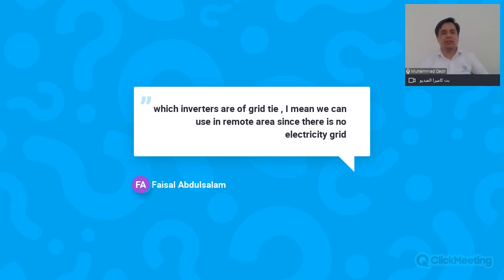The first question is from Faisal Abdul Salam. He asked, what inverters are off-grid? I mean, can we use them in remote areas, since there is no electricity grid? Faisal, on-grid means these inverters require the grid at all times to provide an output. So inverters for an off-grid area are different compared to the inverters we spoke of today in the installation mode. Huawei will soon launch such inverters which can be used for remote locations as well as off-grid or standby applications.